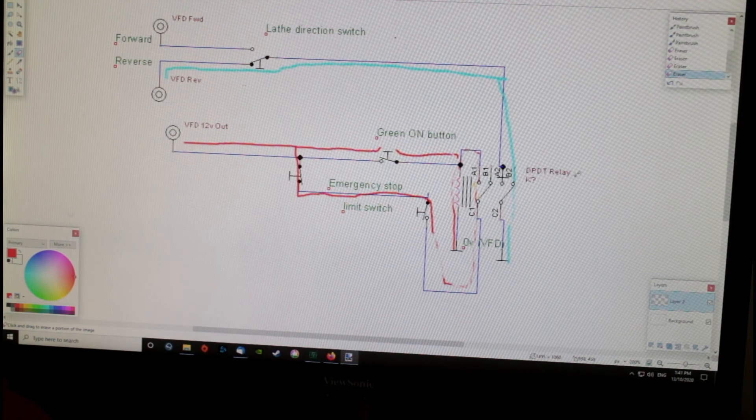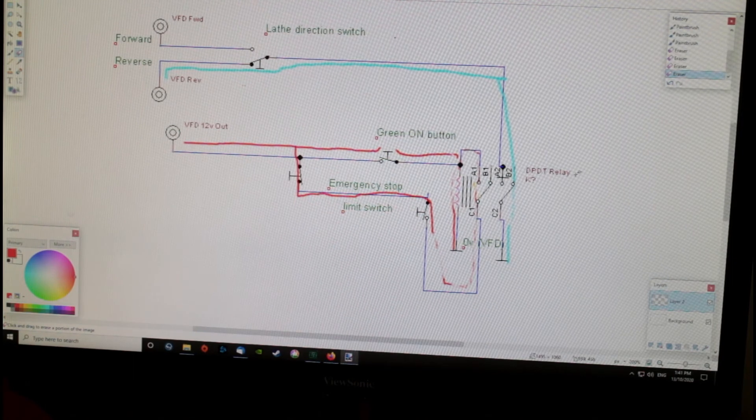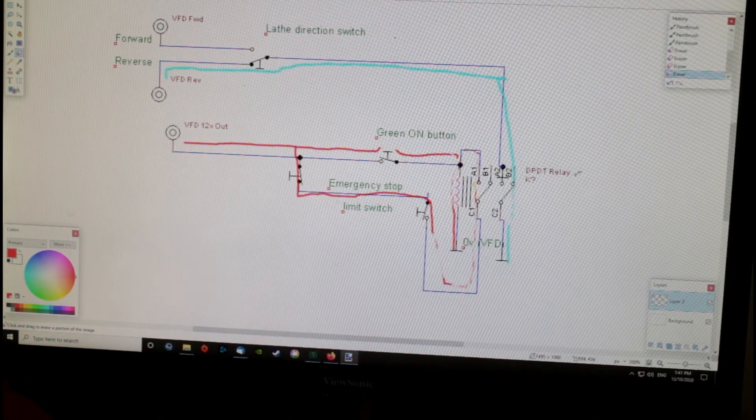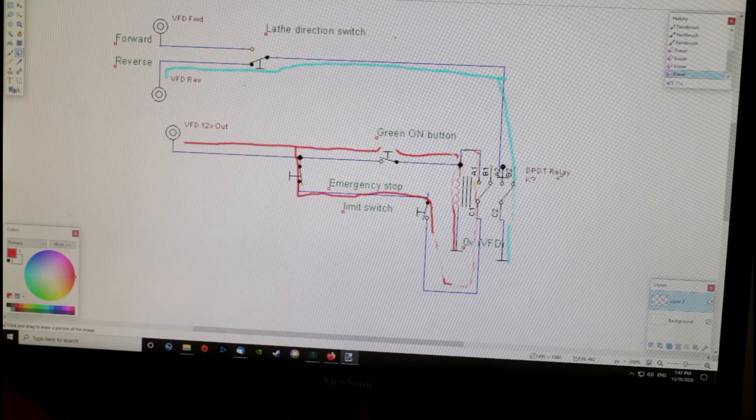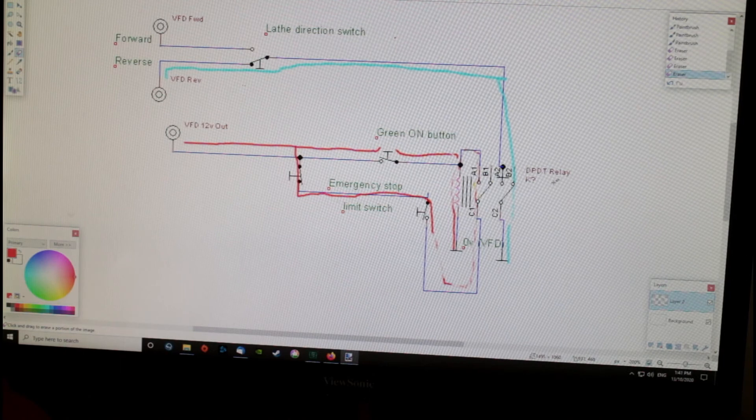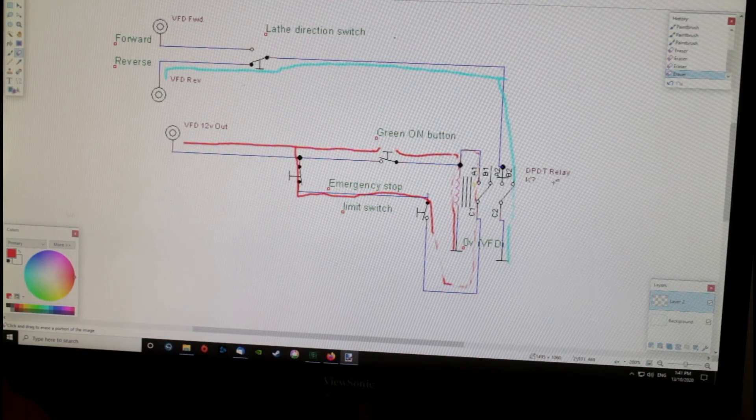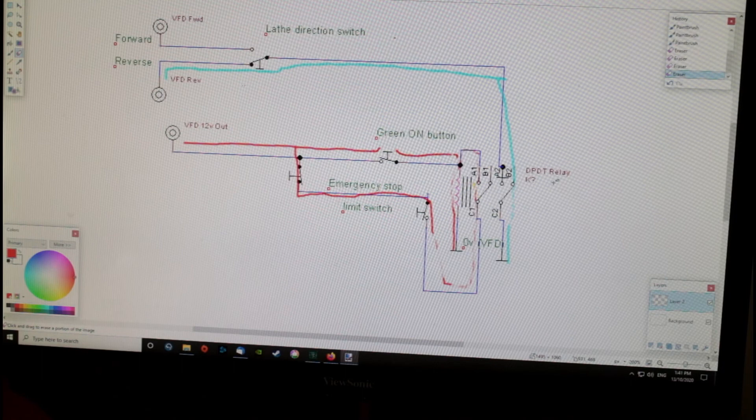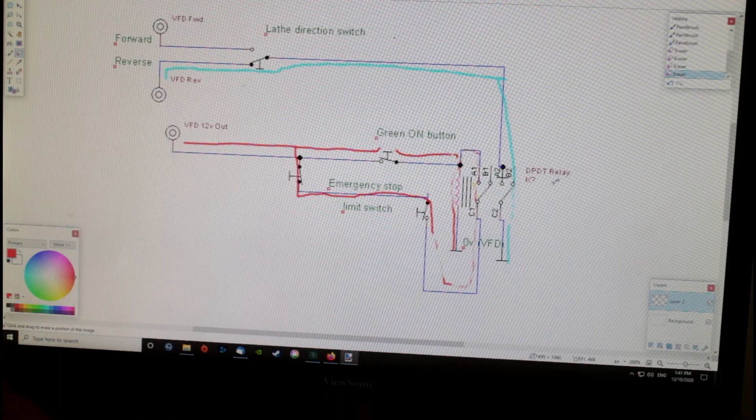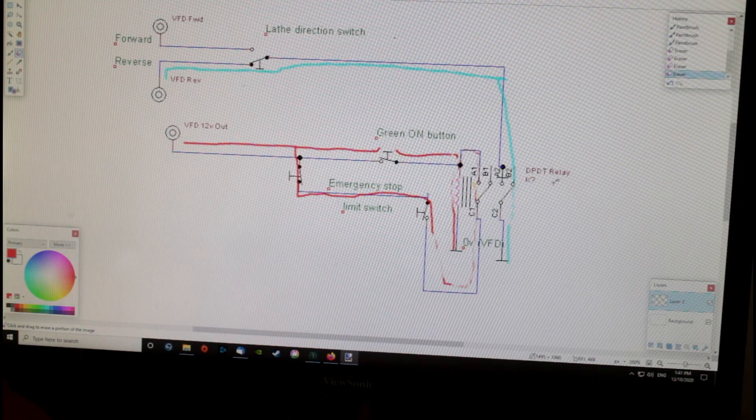That's basically how the circuit works. If you try to use any sort of switching on the output side of the VFD, it will kill it. It will kill the motor, the VFD, or both. They're not designed for it. You cannot have the three-phase connected and disconnected at the motor.